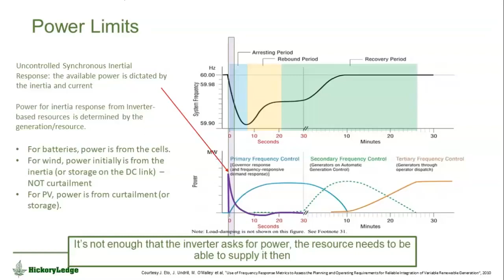Well, there needs to be a source for the power from the other resources. Easy to see from batteries. In practice, it comes out of the inertia of the wind as well, or it could come from energy storage on the DC link of the wind's inverter. For PV, there's no inertia, so the only way you can get these very fast responses is if the PV is curtailed. So it's not just current limits, it's power limits that we have to get right.